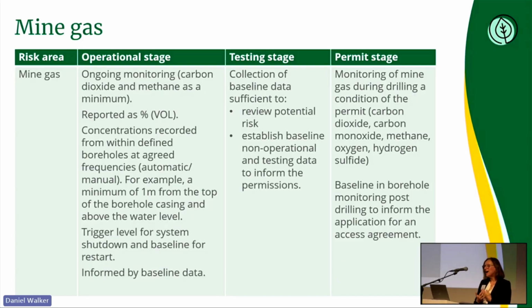What's really critical is that at the operational stage, as a minimum, we'd be looking for carbon dioxide and methane to be monitored. We'd always be looking for standard reporting as percentage volume, and concentrations should be recorded from within the borehole. As a baseline, we're saying a minimum of 1 metre below the top of the borehole, and also in the headspace above the water. Other gases may be required to be monitored.